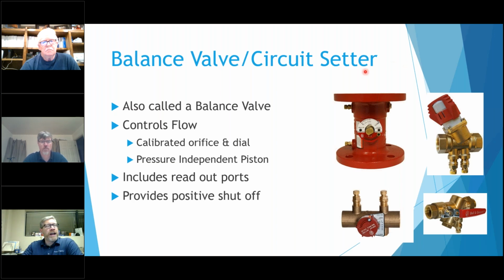There's a couple different varieties here. These two are just a standard circuit setter. It's been around for a number of years. Basically, in these there's a ball valve that you turn the dial and it opens and closes. Depending on what the pressure drop across this is and how open or closed this valve is, you can actually read the GPM going across the valve, which is why they're a little bit more than just a ball valve.